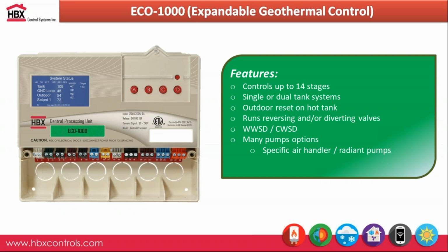In terms of functionality, we can do single or dual tank systems. If you have one main buffer tank, hot and cold, we can control that. Or if you have 2 tanks, one hot and one cold, we can control both of those tanks with one geothermal controller. We also have outdoor reset on the hot tank on the Eco 1000. For the cold tank setup, it's just off of the set point on the Eco 1000, and we can also operate the reversing and diverting valves that switch over from heating to cooling and vice versa. We have a lot of different pump options, which we'll go through later in the slides. But this is the broad general overview of the Eco 1000.